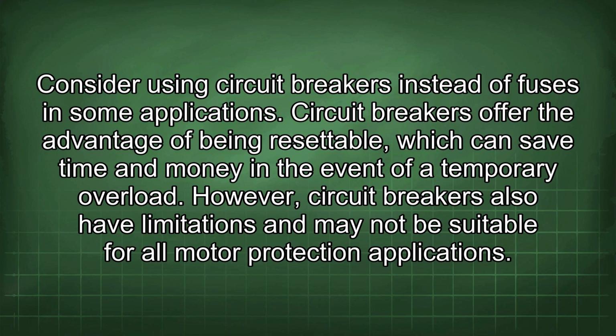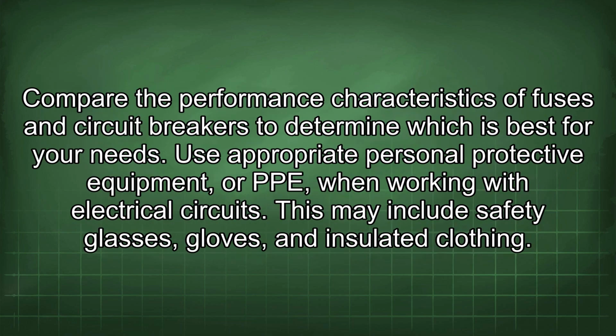Consider using circuit breakers instead of fuses in some applications. Circuit breakers offer the advantage of being resettable, which can save time and money in the event of a temporary overload. However, circuit breakers also have limitations and may not be suitable for all motor protection applications. Compare the performance characteristics of fuses and circuit breakers to determine which is best for your needs.